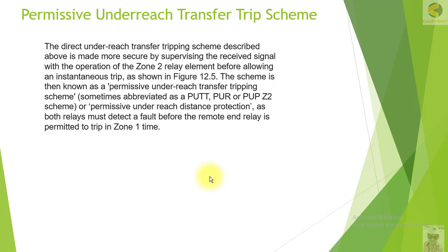Welcome. In this section we will learn about the Permissive Underreach Transfer Trip scheme. The direct underreach transfer trip scheme is made more secure by supervising the received signal with the operation of a Zone 2 element before allowing an instantaneous trip, as shown in figure 12.5. The scheme is then known as the Permissive Underreach Transfer Tripping scheme, sometimes abbreviated as PUTT.